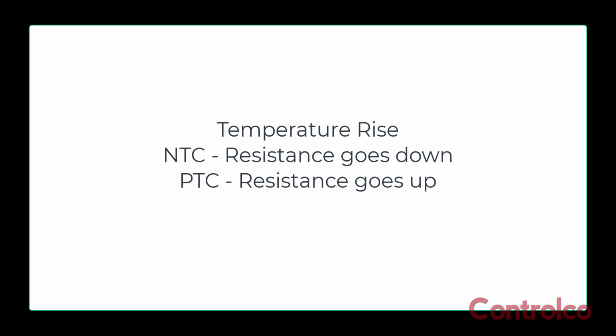Again, you have to go back and look at your controller to see what the controller is rated for as far as its sensor inputs. 90% of dealing with sensors is knowing what the controller can accept at its inputs. Extremely, extremely important. I keep saying this is important. It's really important.